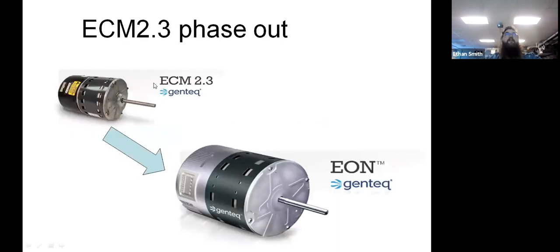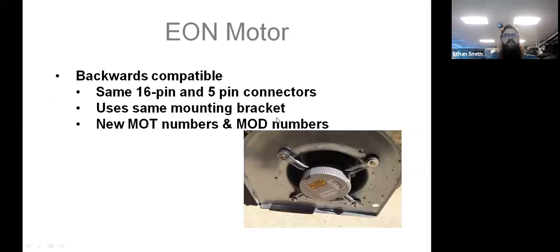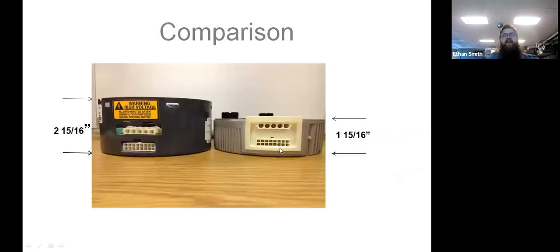Okay. So the good news is that ECM 2.3 was a great little motor. It has been phased out by Genteq, and they've phased that out in favor of their new Eon platform. The Eon motor modules are backwards compatible to the ECM 2.3 motors. It has the same connectors, uses the same mounting bracket, but they've reduced the controls package size. So this is sized to go into their motor. Their motor has space to accommodate those two bumps.